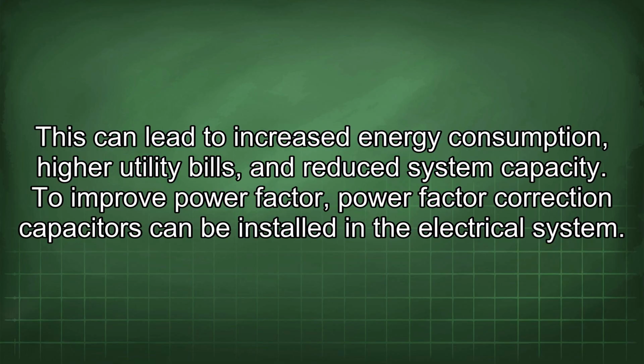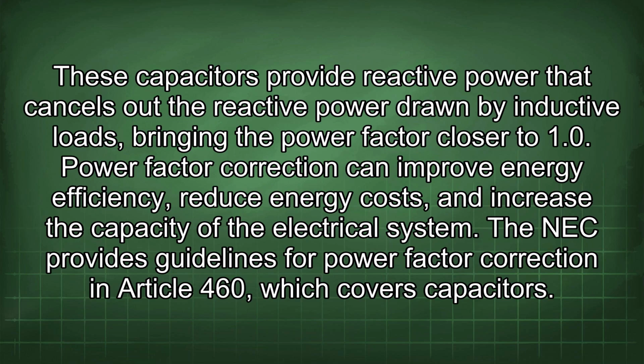To improve power factor, correction capacitors can be installed in the electrical system. These capacitors provide reactive power that cancels out the reactive power drawn by inductive loads, bringing the power factor closer to 1.0. Power factor correction can improve energy efficiency, reduce energy costs, and increase the capacity of the electrical system.